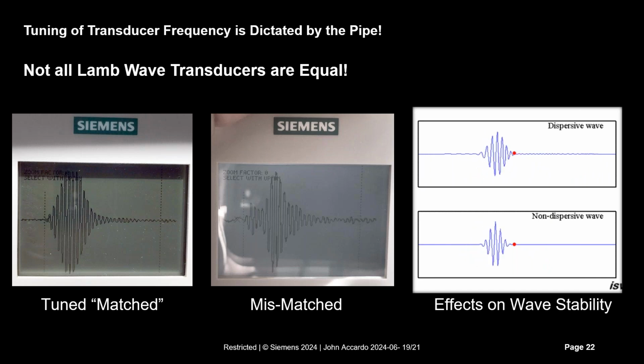And as I said earlier, not all Lamb wave transducers are equal. Just because a company says that they have Lamb wave, they don't match them to the pipe. They pick them based upon the closest match to the wall thickness, but there's no frequency sweep done to further tune them to what the pipe actually resonates at. And that's a critical difference.